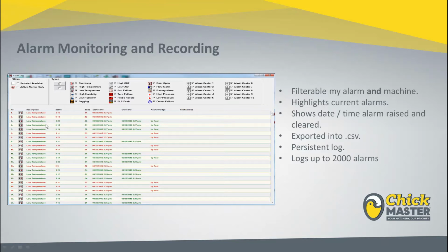The other information down here, as well as the start time and the end time, you'll note an acknowledge by and a notification. The alarm log indicates if there was an email or text message sent out to notify. Acknowledgement means that somebody in the hatchery has acknowledged the alarm at that time, and therefore if you're getting a notification, it'll have the name of the person who acknowledged the alarm.